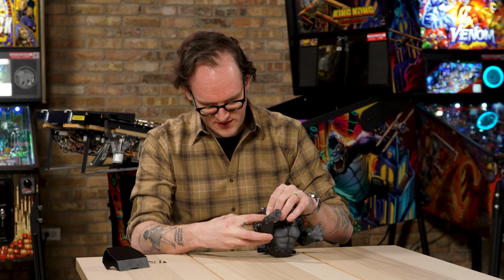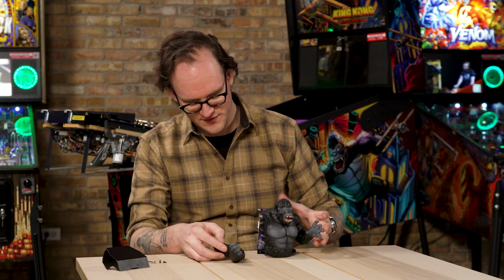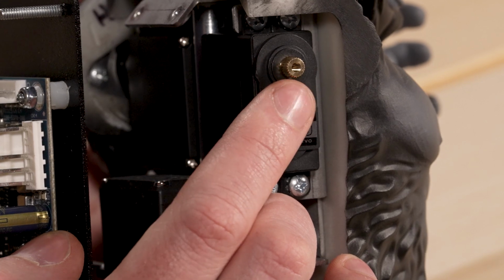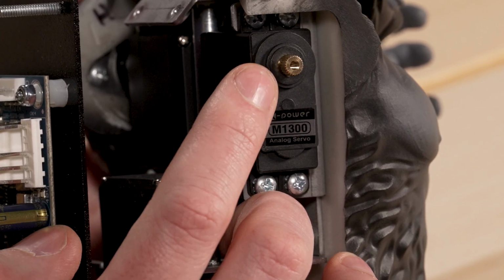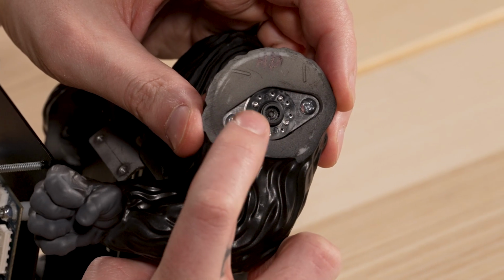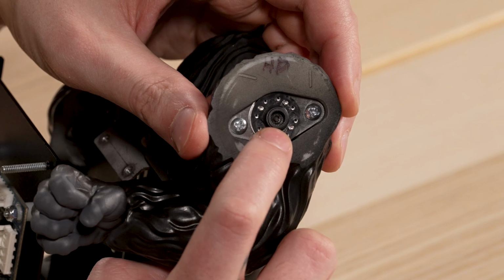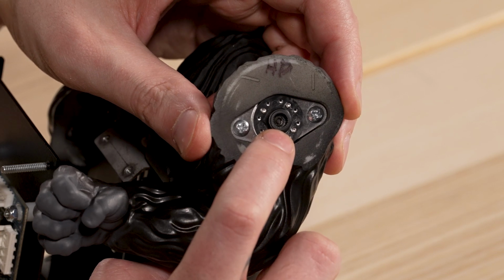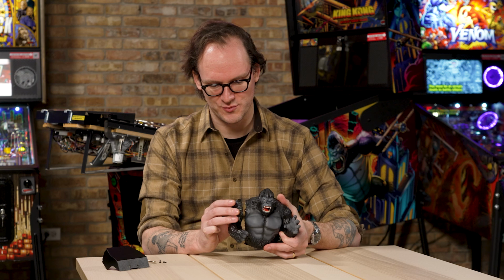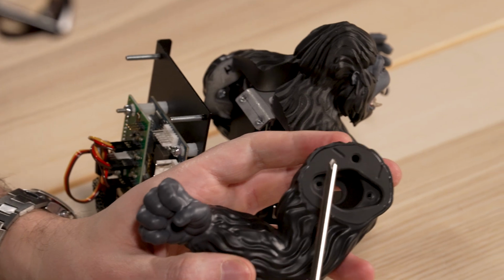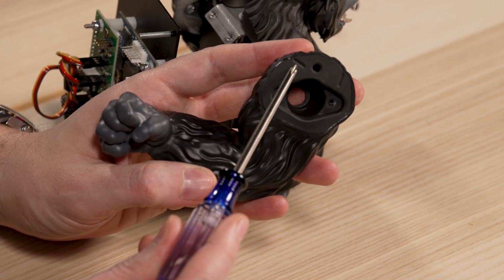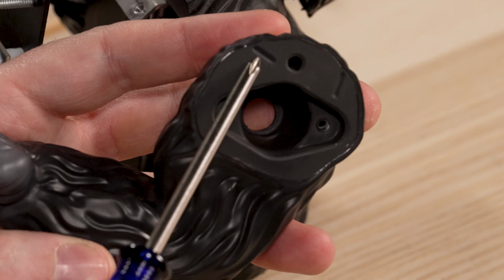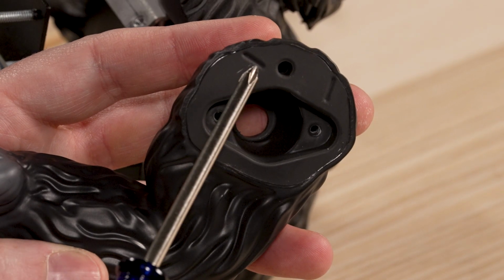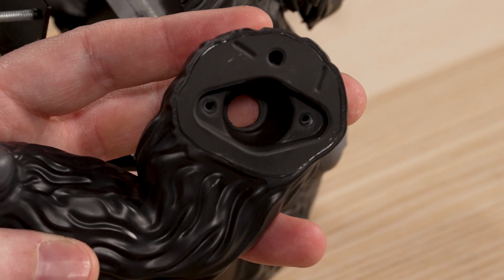When we get that loose and pull the arm off of the servo motor, you'll see that the servos have a 25-tooth spline. What that means is this arm has a matching spline with 25 indentations. Unless you put this arm on in the absolutely exact same position you removed it from, it is going to be out of calibration. While we're looking at the arm, we can also see some calibration marks. These are marks that you will use when recalibrating the assembly as a visual guide when you're setting the calibration in software.